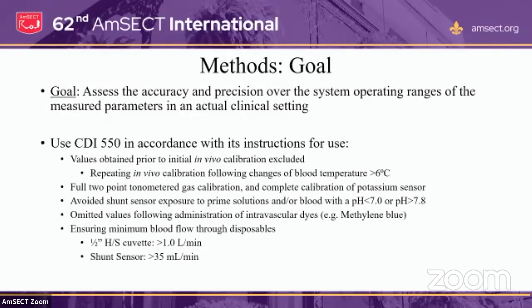So I used it in accordance with its instructions for use. And all the values obtained prior to the initial in vivo calibration were excluded. Sometimes my first sample was before cardioplegia administration, sometimes it was after, and all of the subsequent samples were suitable for analysis. That first sample was omitted. I did a full 2-point tonometer gas calibration and a complete calibration of the potassium sensor. So if there was an emergent case and I wasn't able to do the full gas calibration, I excluded it from analysis. I avoided shunt sensor exposure to prime solutions and or blood with a pH of less than 7 or greater than 7.8. And I was mindful of the administration of intravascular dyes such as methylene blue. The sensors work on optical reflectance and fluorescence, and that would compromise the accuracy of that.